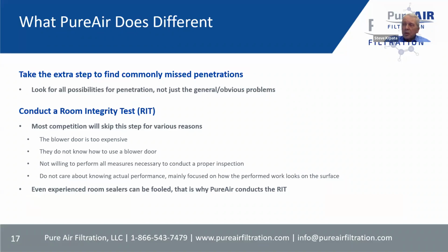So what do we do? What does Pure Air do differently than everybody else? First of all, we're very experienced. We've done thousands of rooms. Through our history, we generally find all of the bypasses and penetrations because we know where to look, and we have a lot of tools in our toolkit to do that. Even if we miss something through experience and visual inspection, we'll pick it up in the room integrity test and find it using smoke tubes or smoke pencils. We would assure ourselves and you that the job that's been done is good and is the best that it can be for that space, and we can document that.